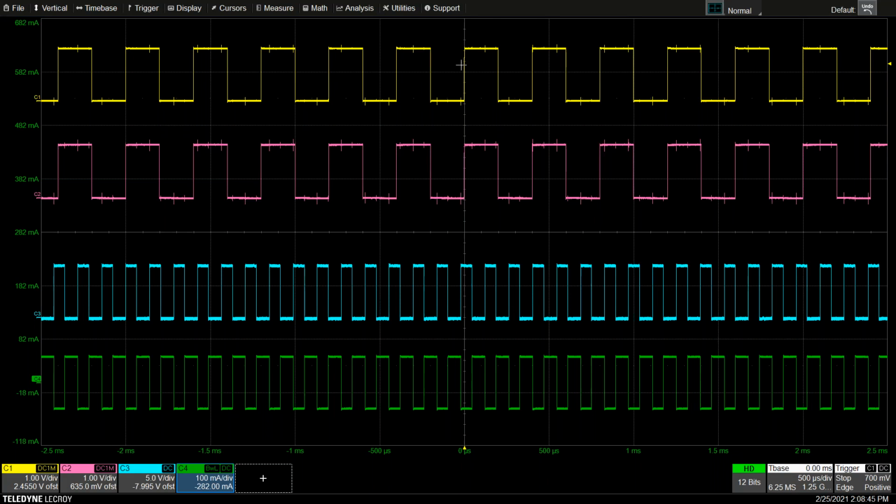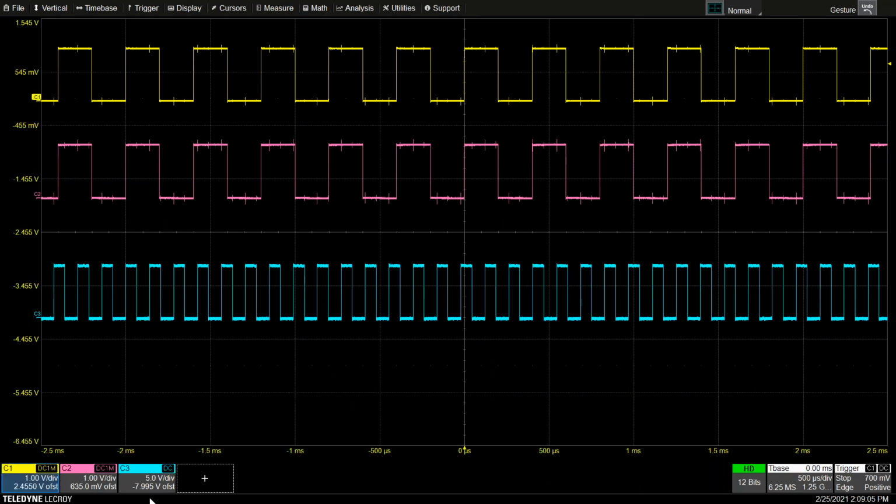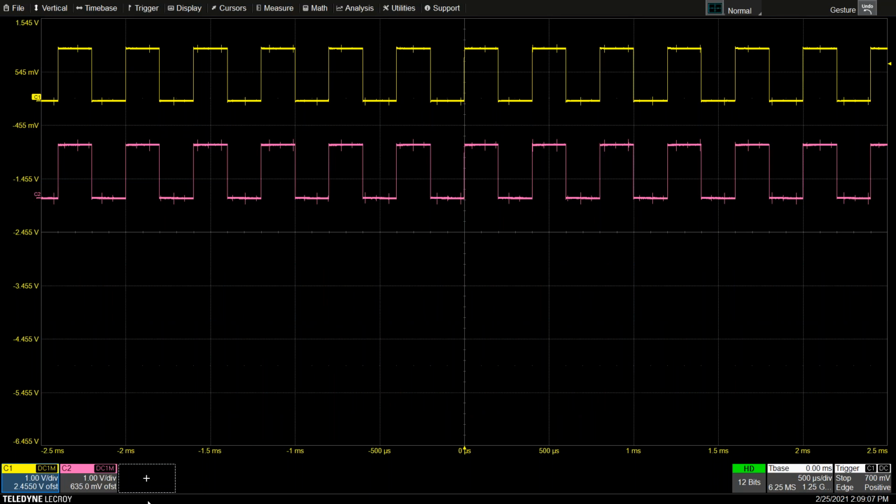So this is good, right? But what if we wanted to make amplitude measurements here? And amplitude and even timing measurements are good. Did us reducing the amplitude of these signals affect our measurement? So let's dive into that. So what I'm going to do is flick off channel 4 and 3. So we're now at these 2 waveforms. Now channel 1 and 2 again are tied together to the calibrator. And now let's go back live, and I'm going to disconnect this DSQ source. It's adding a little noise to my channel 2. There we go. And so we are live.